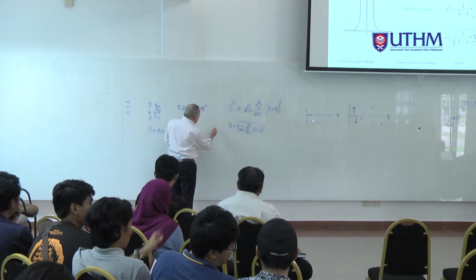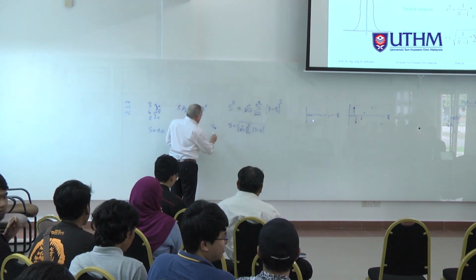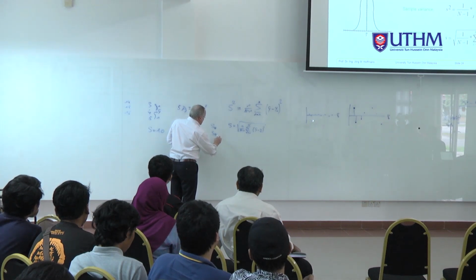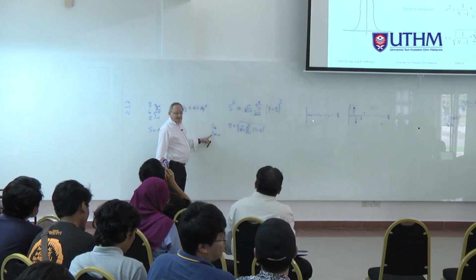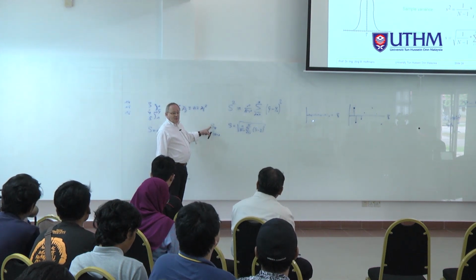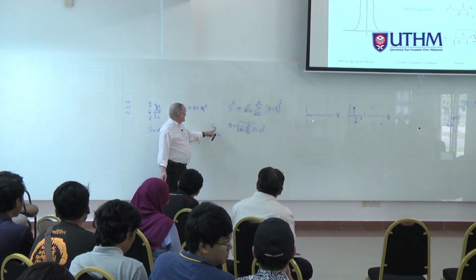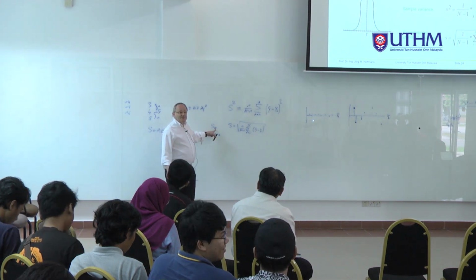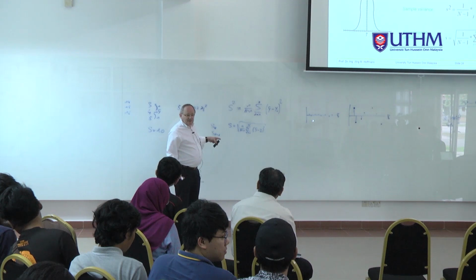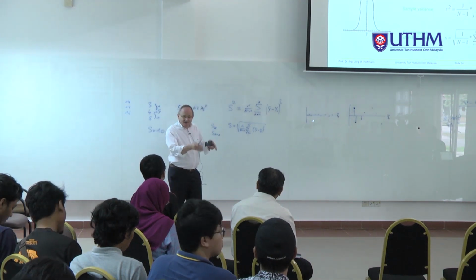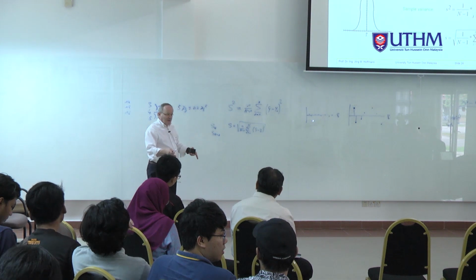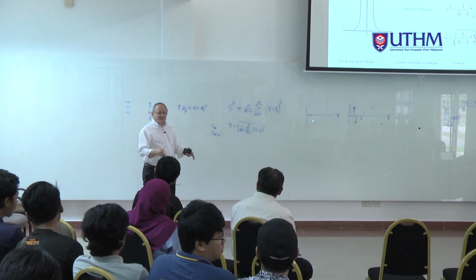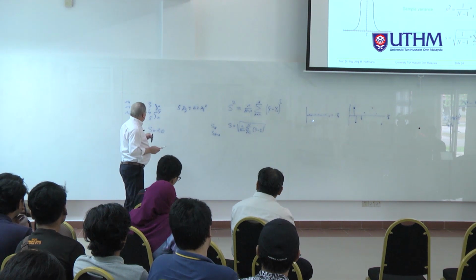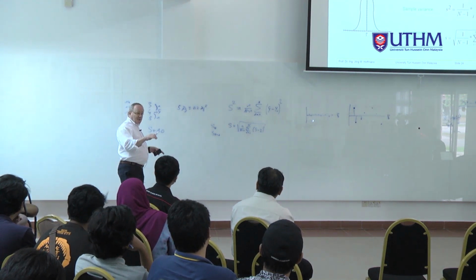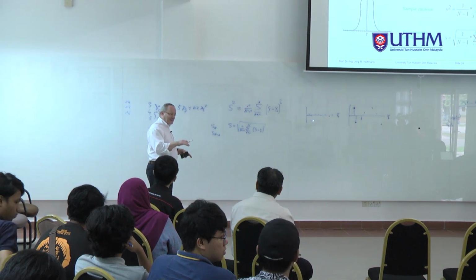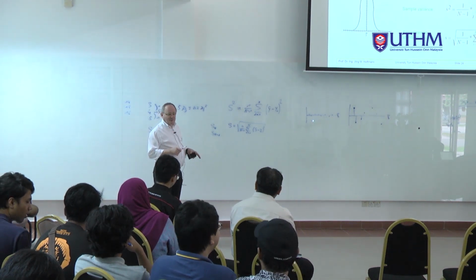That is then written as Sn. What we need is n minus 1. That is what we need. This is only for the mathematicians, because this is under the condition that the n is going to infinite. But that we cannot do in practical measurement. In practical measurement, we have a limited number. It can be high, of course, but never infinite. So therefore, you can check with these 3 numbers your pocket calculator. When you get exactly 1.0, then it's the right formula that you have.